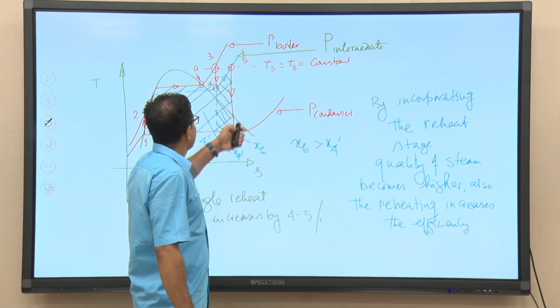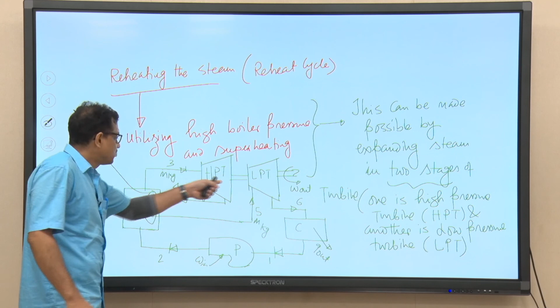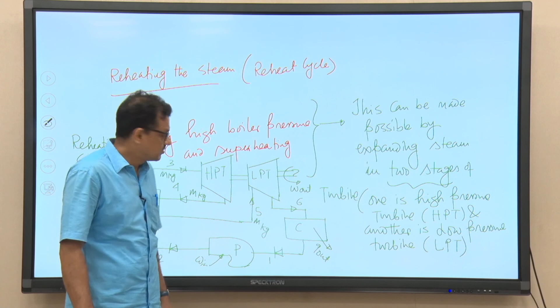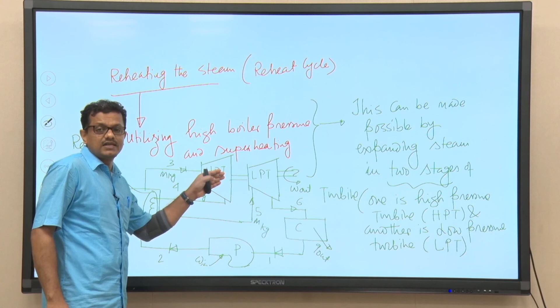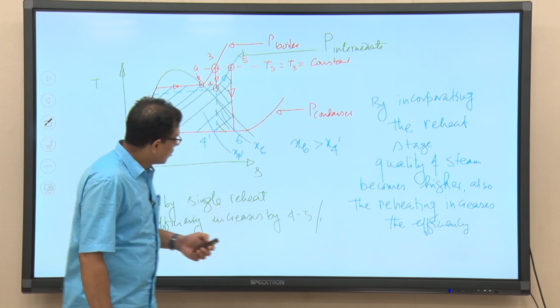So, even with one reheat stage, you can understand so many things. You have to have pipeline, you have to have 2 different stages of turbine, you have to have one heating coil. So, both installation cost as well as operational cost are involved. But if we can have a specific turbine blade material which can withstand high temperature, then perhaps it is not required to go for the reheating method, instead we can use the superheating stage. So, though reheating provides all these favorable features, even then if we can have a specific material to fabricate turbine blades, and if that material can withstand high temperature, then superheating will be more viable than the reheating stage.